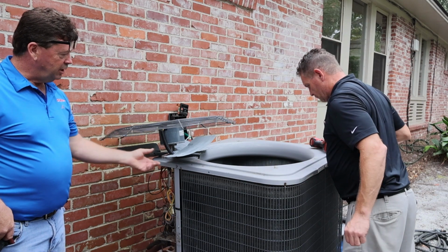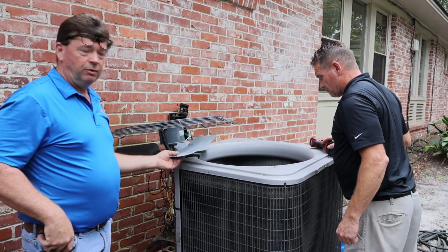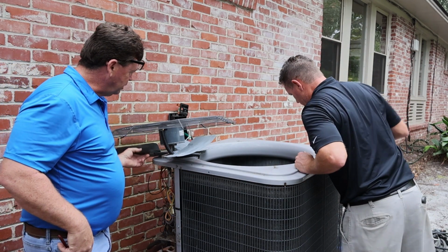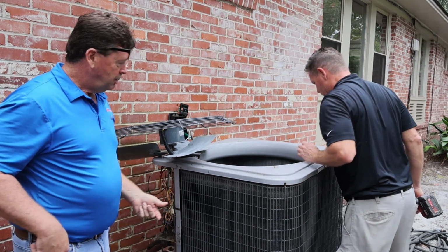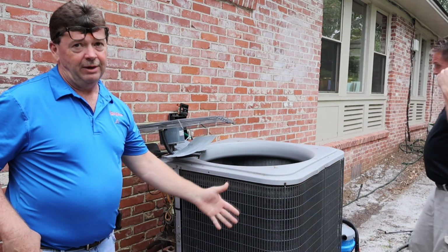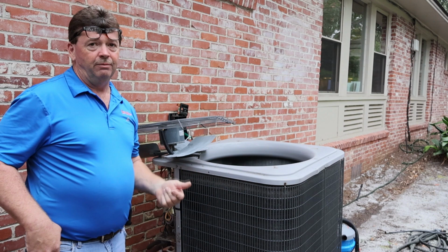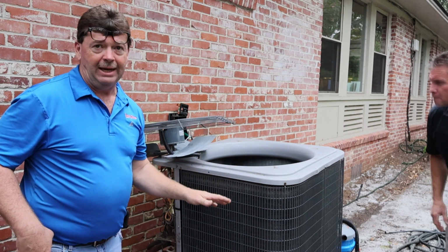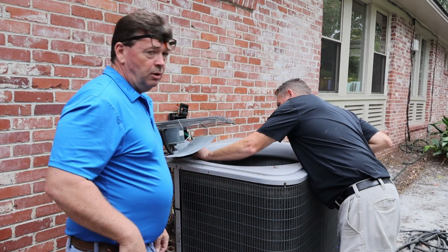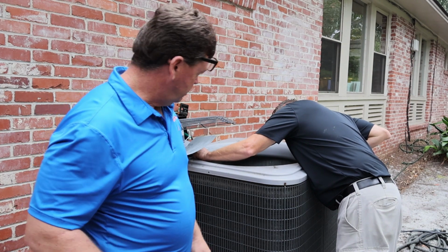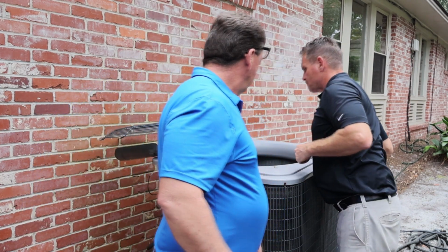We were able to set it up. We feel pretty comfortable that we're not putting any tension on the blades that could cause some imbalance. But if we did feel that way, we would have to take it off. I know it's a little more work, but I'd rather do that than have to come back and put a new blade on. So we're in the process of cleaning out the condensing unit now, which is full of leaves.